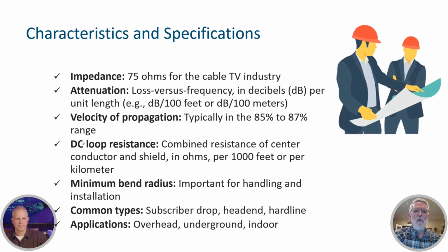DC loop resistance is something that's important, particularly if you're designing the network powering. You've got to know the loop resistance. That is the combination of the resistance of the center conductor over a specified length, typically 1,000 feet, and the shield over the same distance. So it's 1,000 feet here and per kilometer in other locations. And later on, you're going to show us how to measure that. So I'll show you conceptually how it's measured, because the manufacturers measure it using laboratory grade instruments that can measure very, very low resistances. When you get down into less than an ohm resistance with a conventional, I'll call it consumer type ohm meter, the accuracy can be questionable. So that's why they use some really high end lab grade stuff for that. But yes, I'll show the fundamentals of how that's measured.